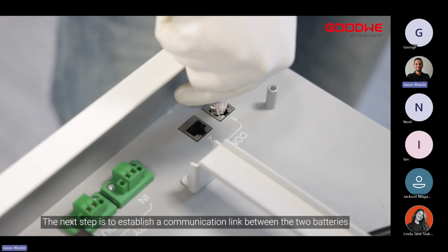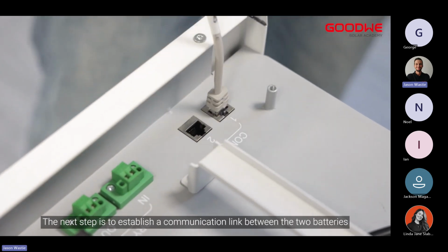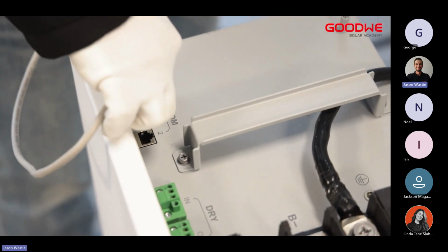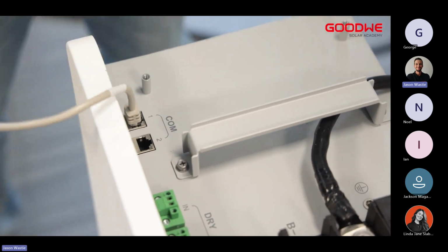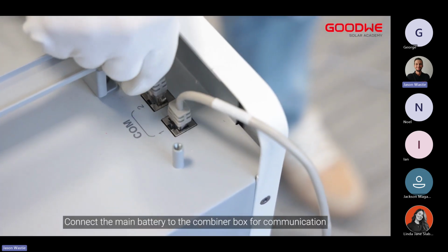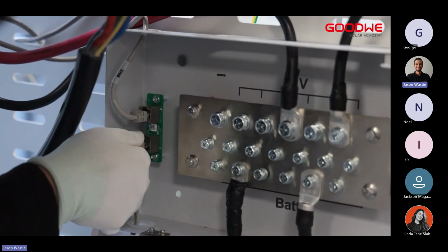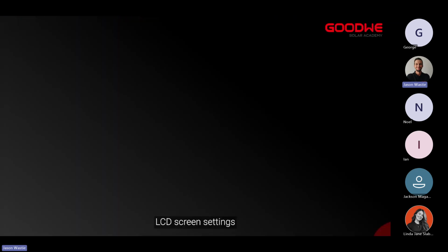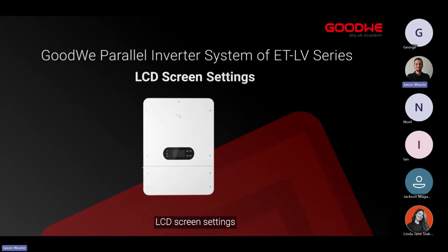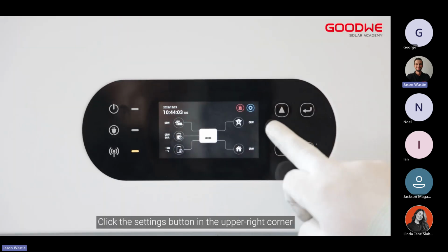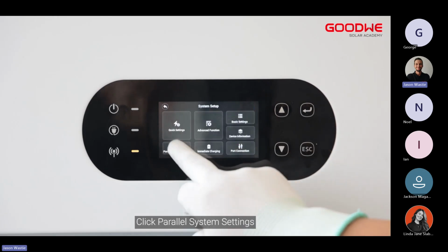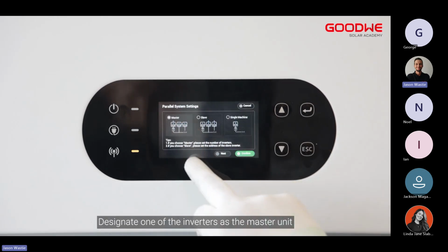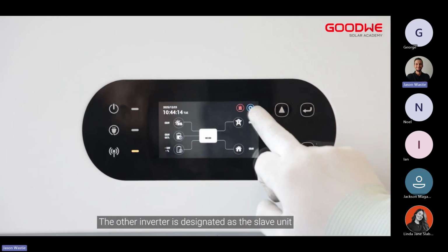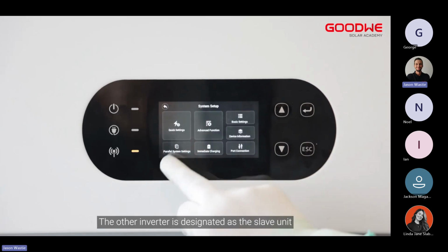The next step is to establish a communication link between the two batteries. Connect the main battery to the combiner box for communication. LCD screen settings. Click the settings button in the upper right corner. Click parallel system settings. Designate one of the inverters as the master unit. The other inverter is designated as the slave unit.